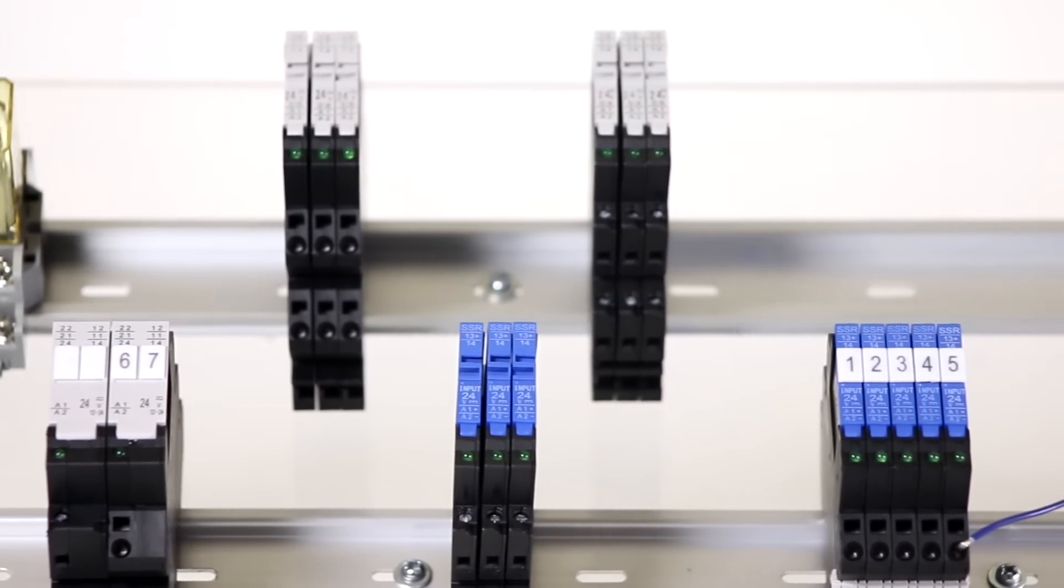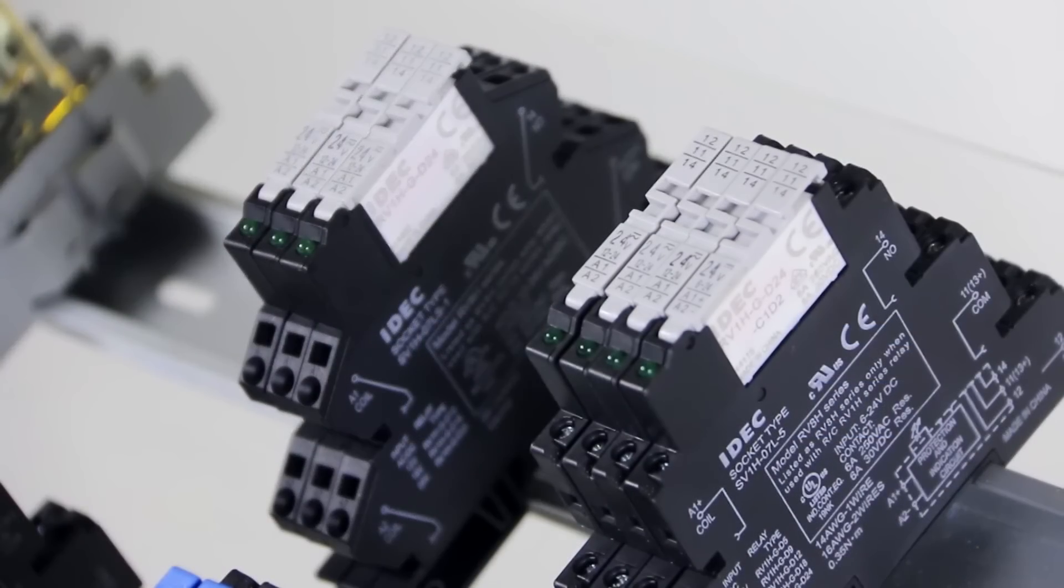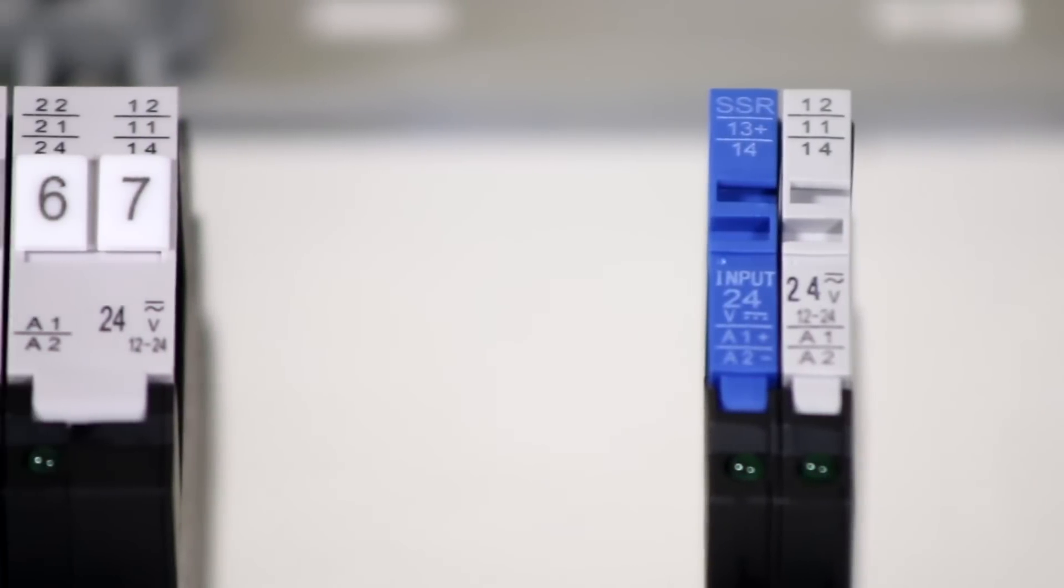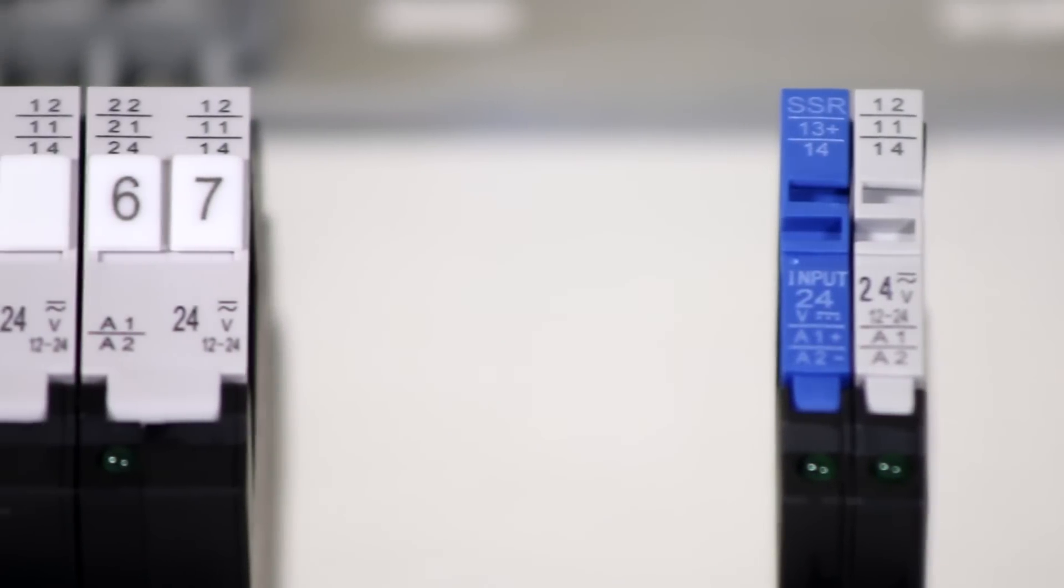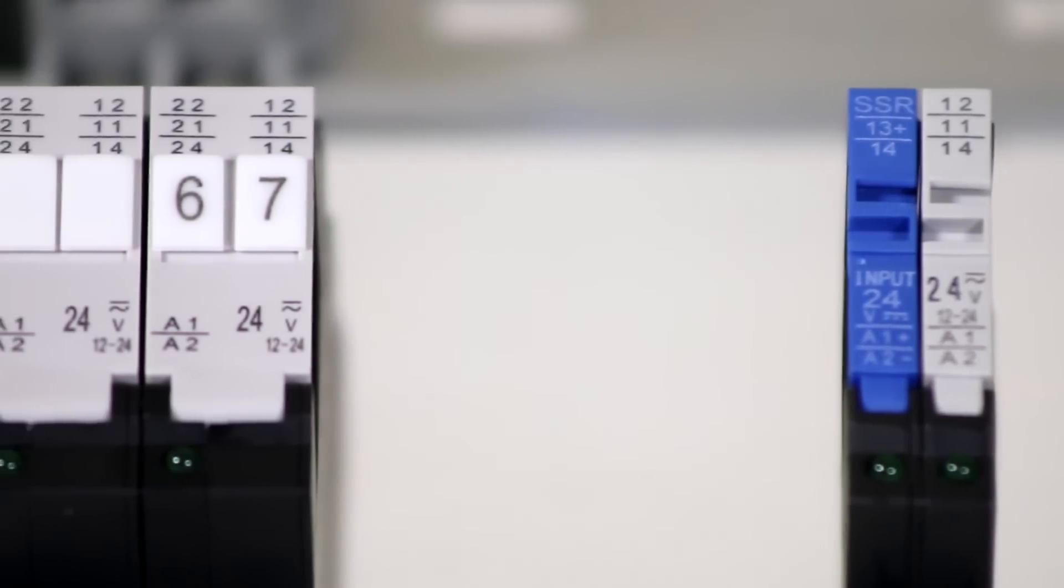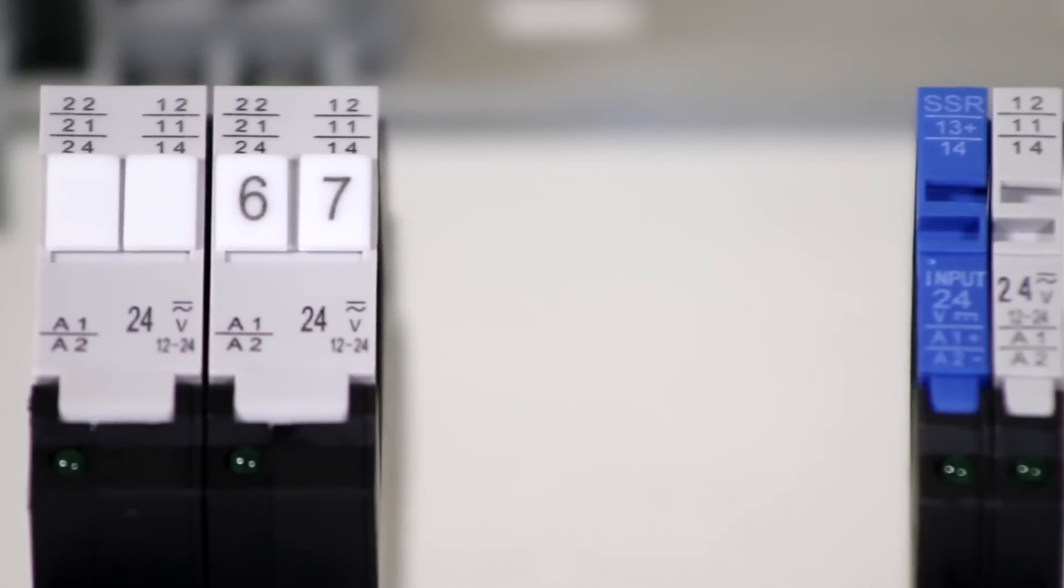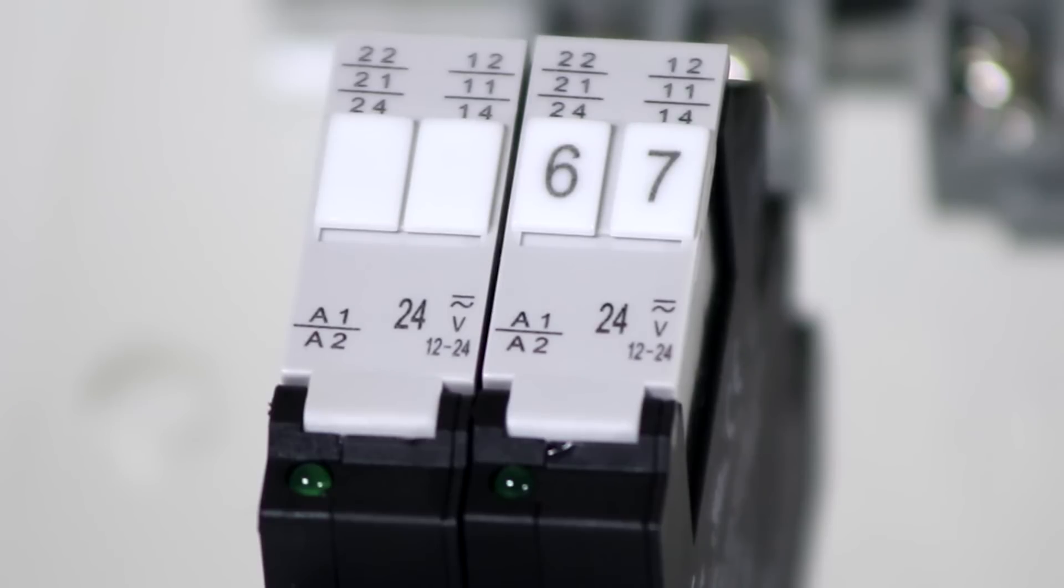For both the solid state and electromagnetic versions, single pole models are only six millimeters wide. Electromagnetic double pole eight amp and high capacity single pole 16 amp models are just 14 millimeters wide.